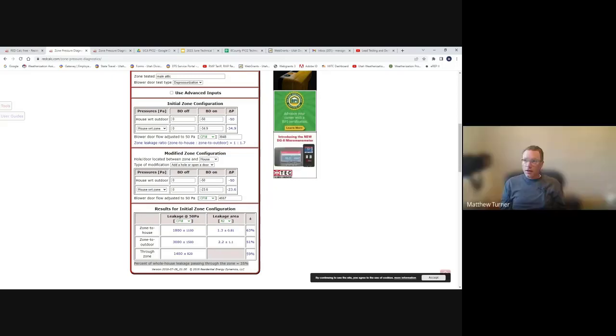Yeah, I hope you can see it's just those 4 numbers, and once you've done it once or twice, even when I've done it out in the field, I literally just write down the 4 numbers in my notes, and then when I get back. The thing you want to remember is just what Roger said. You want 6 to 10 Pascal difference.